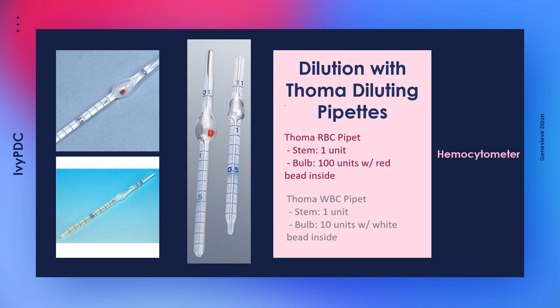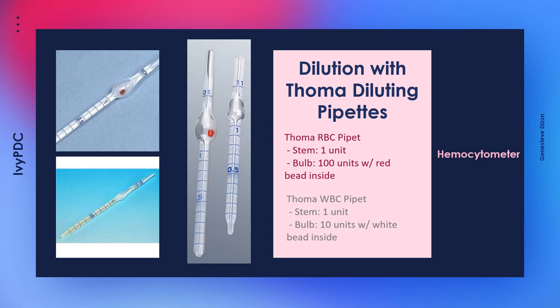There are two types of Thoma diluting pipettes: the RBC pipette and the WBC pipette. Both can contain up to one unit of fluid inside their stems. The RBC pipette is bigger and can contain up to 100 units of fluid in its bulb, while the WBC pipette can only contain up to 10 units. Because of this, the RBC pipette can perform higher dilutions. The total units for an RBC pipette is 101, while the total for the WBC is only 11.